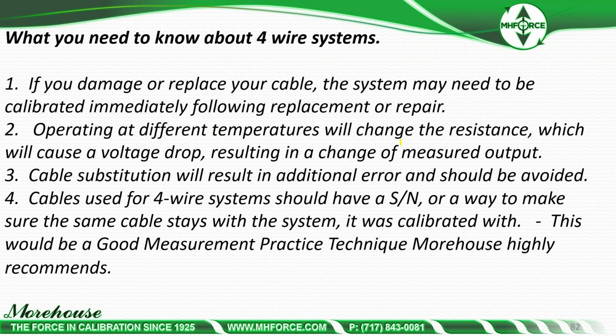So here's what you need to know. If you damage or replace your cable, the system may need to be calibrated immediately following replacement or repair. Operating at different temperatures will change the resistance, which will cause a voltage drop, resulting in a change of measured output. Cable substitution will result in additional error and should be avoided. Cables used for 4-wire systems should have a serial number or a way to make sure the same cable stays with the system it was calibrated with. This would be good measurement practice technique Morehouse highly recommends.